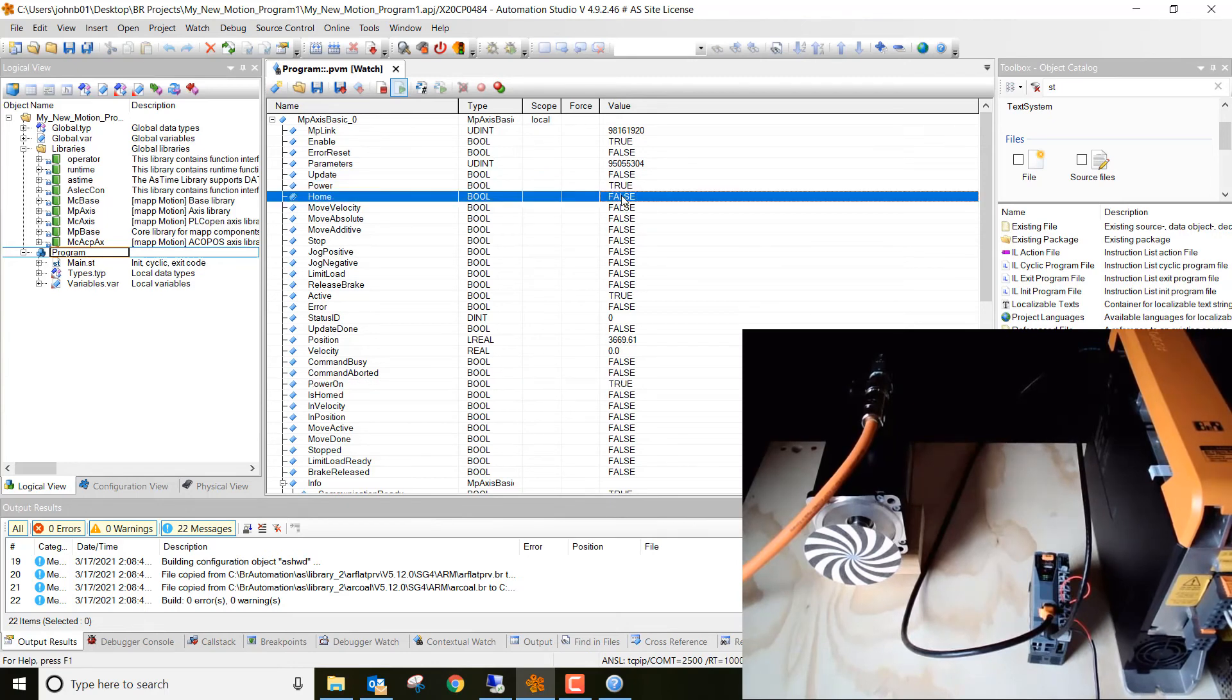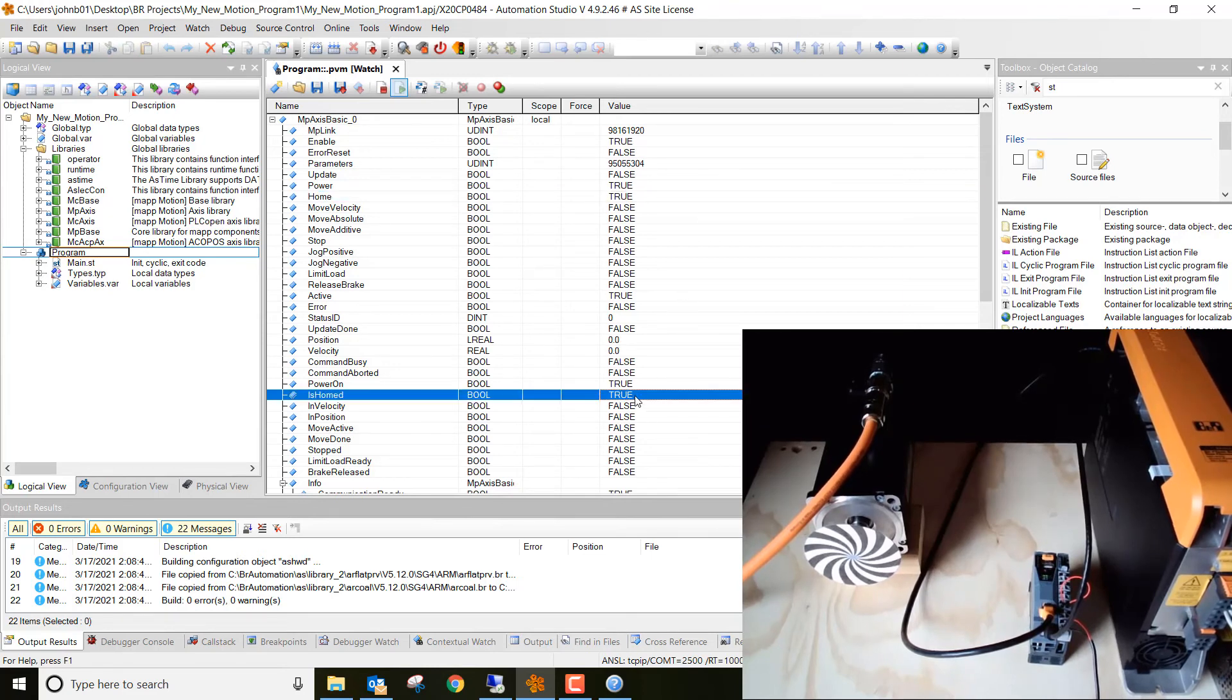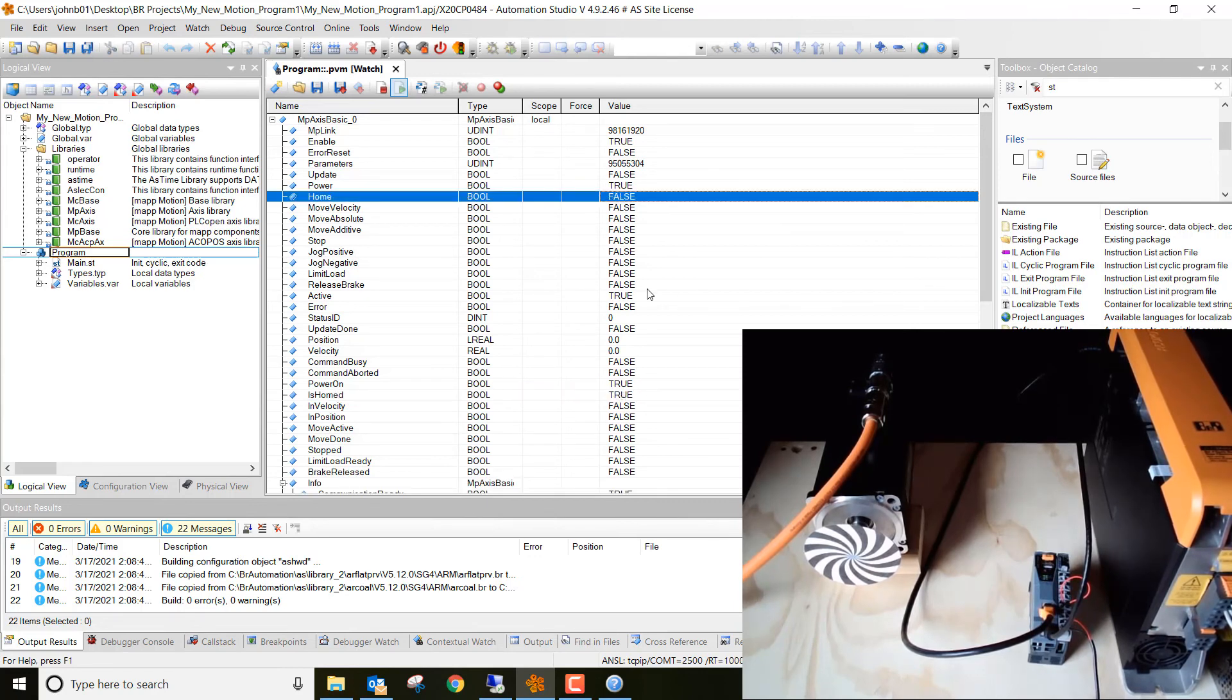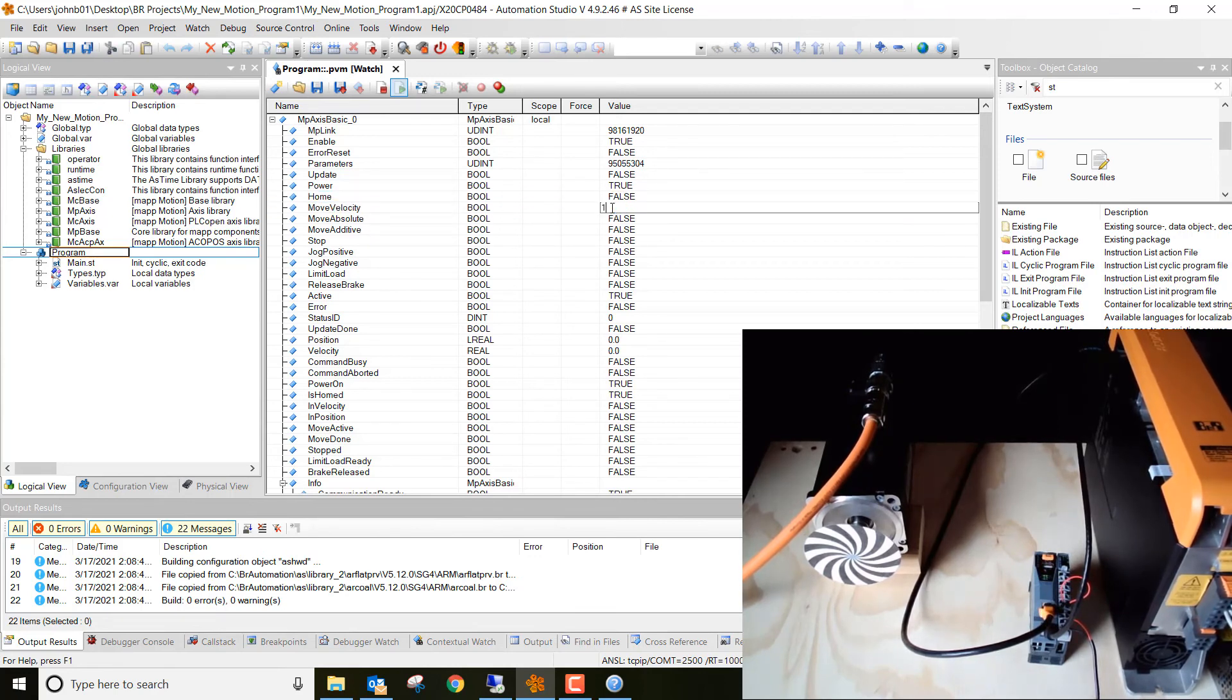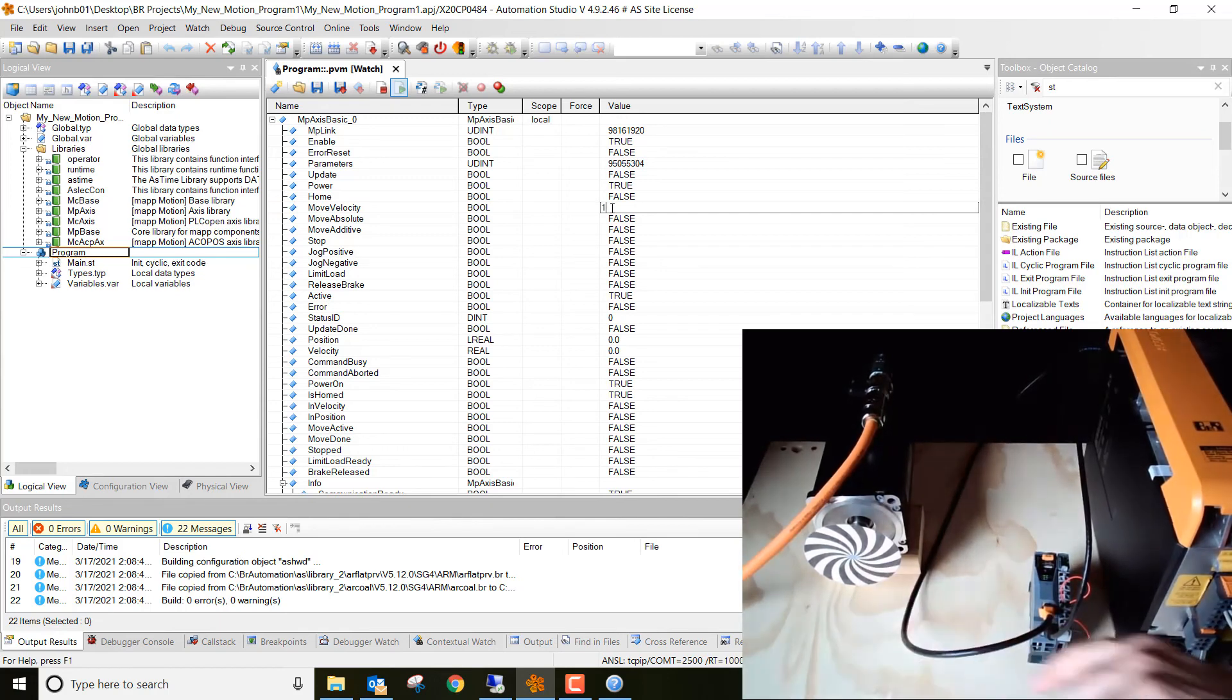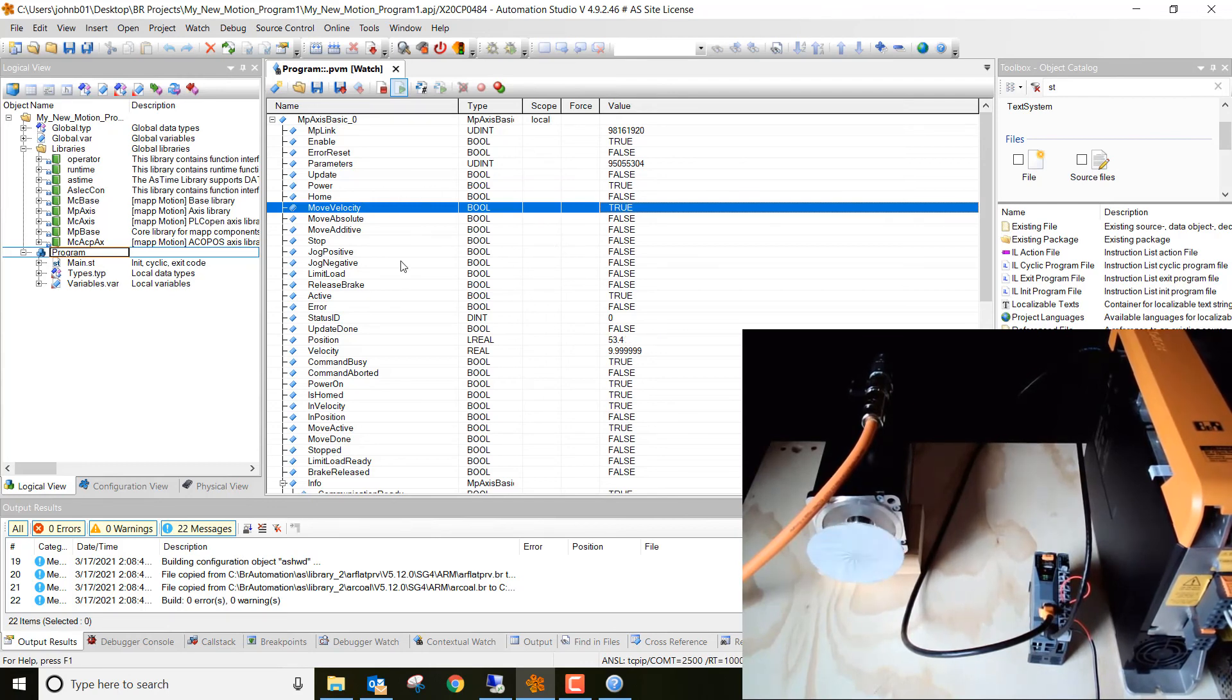Next we want to home it. So go ahead and click home. And then you can see right down it is homed. So go ahead and we can change that back to false again. It's going to stay homed. And then we can do a move velocity, a move absolute or a move additive. Let's go ahead and just do a move velocity for now. So go ahead and change this to one. Watch the spin. Watch the motor spin. All right guys, we actually are able to spin the motor. We can now take these different parameters in here and load this into a program.